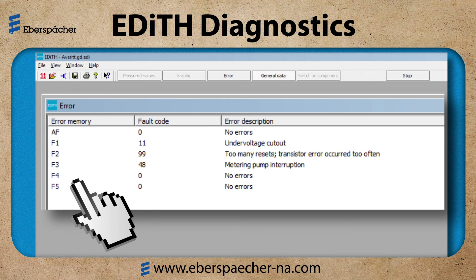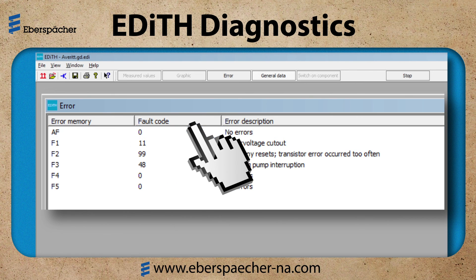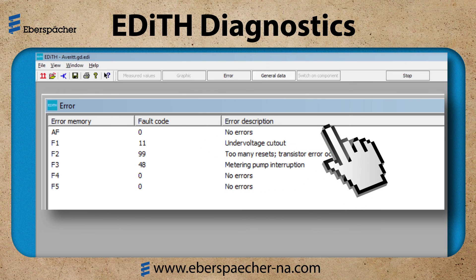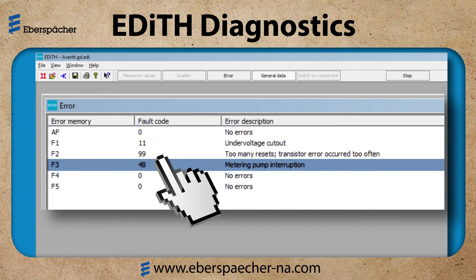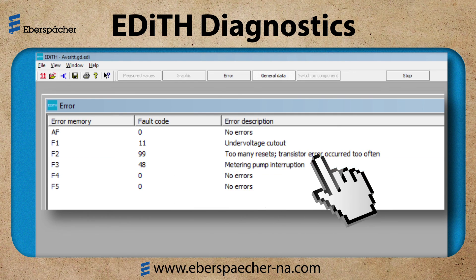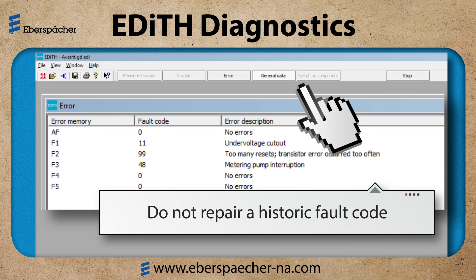Once a new fault code occurs, the old ones will move down a position. AF reads zero, meaning when the heater test was activated, there was not a fault detected. As an example, if I unplugged the fuel metering pump, this would create a code 48, metering pump interruption. AF would read 48 and F1 would read 48. The historic fault codes F1 to F5 do not have a timestamp associated with them, meaning I do not know when they occurred. I want to record these for reference, but do not repair a historic fault code.